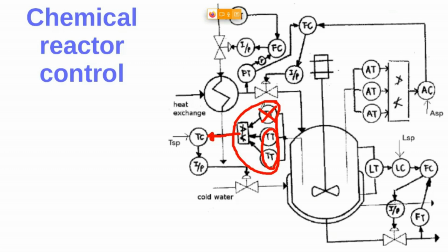But you don't know how it will fail. You don't know if the measurement will be the lowest value in the scale or the highest value in the scale. That's why you use not the maximum nor the minimum value. So if you have one that is giving you the minimum value, the other one a value, and another one that is a value so close or similar to that, if you don't take the maximum and not the minimum, you for sure will take a correct value, right?